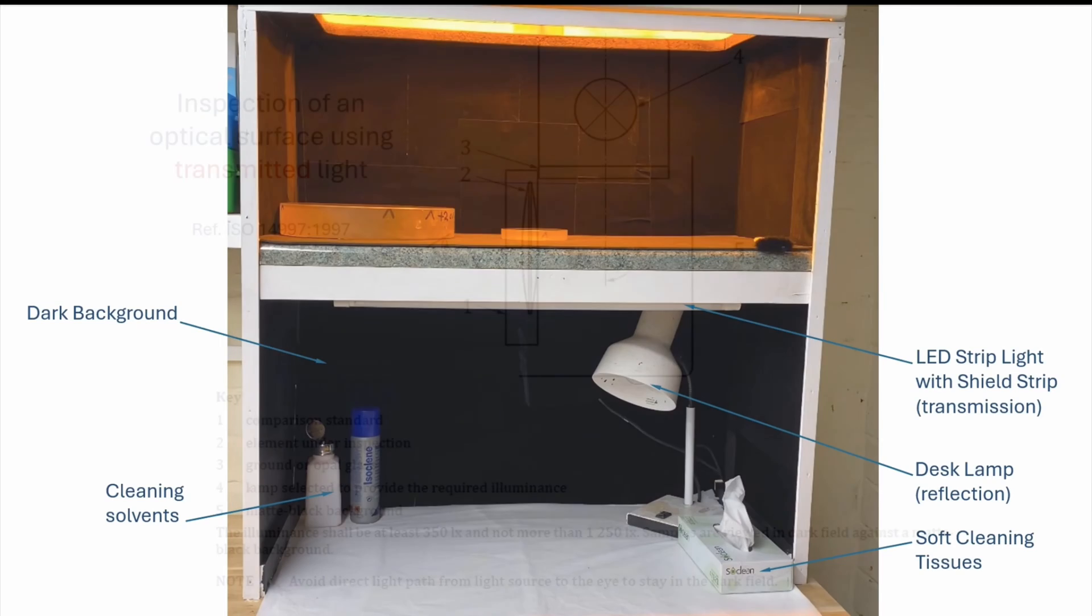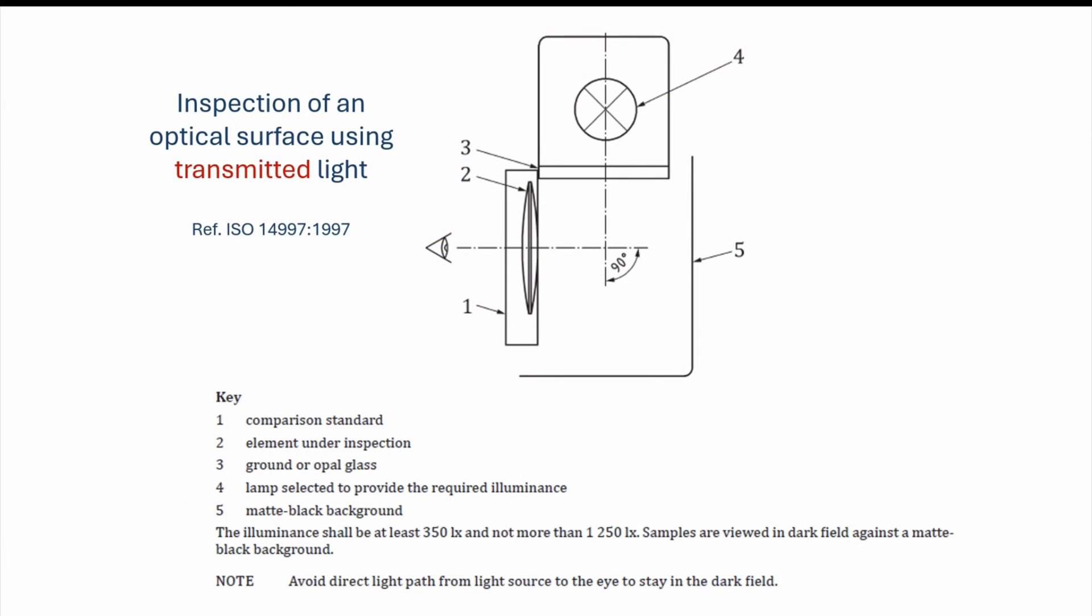Let's have a quick look at the booth. The lower section is intended for inspecting the surface quality of optical surfaces. We're really looking for things like scratches and digs or edge chips. To do that effectively you need to have a dark background with an illuminated foreground. For transmission, if you're inspecting in transmission, you need the strip light at the front there.